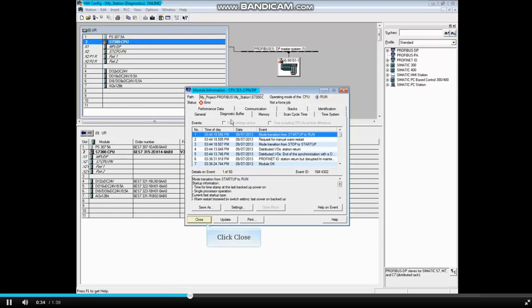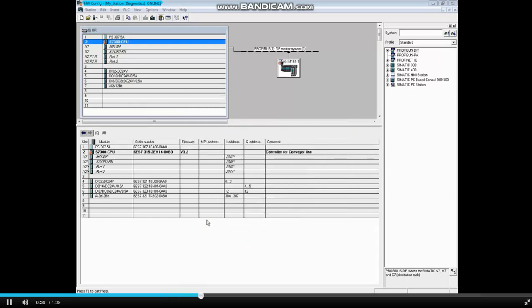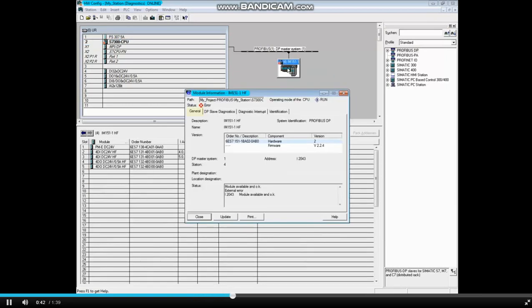Close the CPU Module Information tool. Double-click on the IM151-1 module of the ET200S station. The General tab says that the IM151-1 module is okay, but there is an external error.